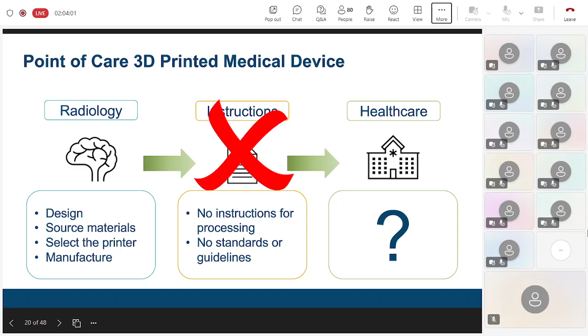So basically, the hospital is the manufacturer of the 3D printed medical device. They have sourced the printer, they have sourced the material, and they now will print that 3D medical device in the radiology department. For this reason, there are no manufacturer instructions, because the hospital is now the manufacturer. The hospital, or rather the cross-functional implementation team, would now need to develop the instructions for use and for reprocessing. FDA apparently is currently writing guidance on how hospital 3D printing will be regulated. However, I don't have any update on that at the moment.